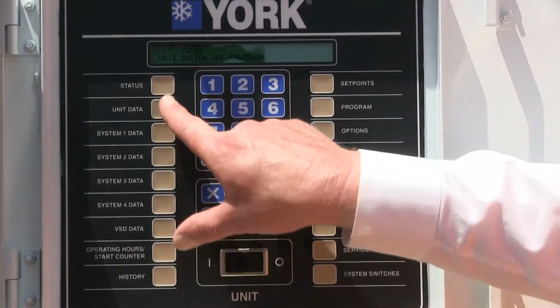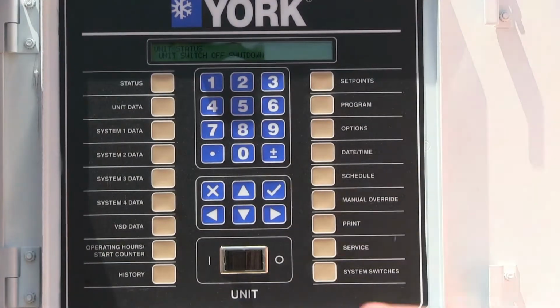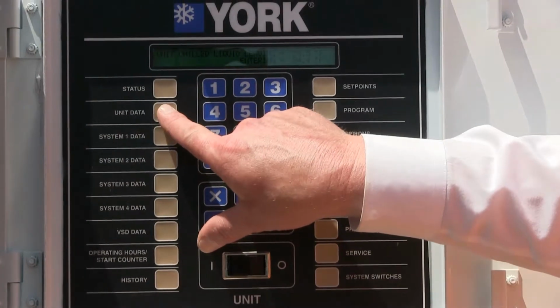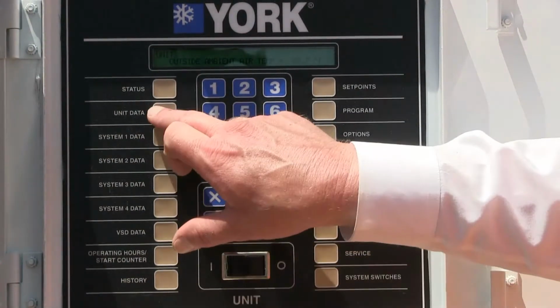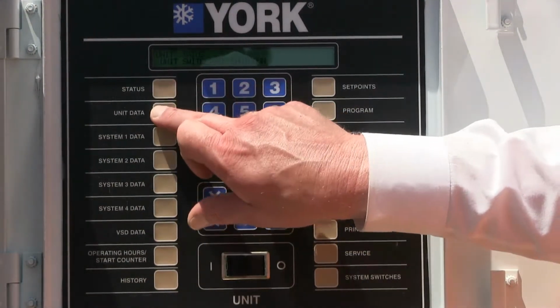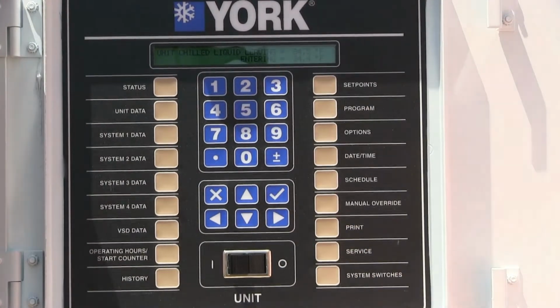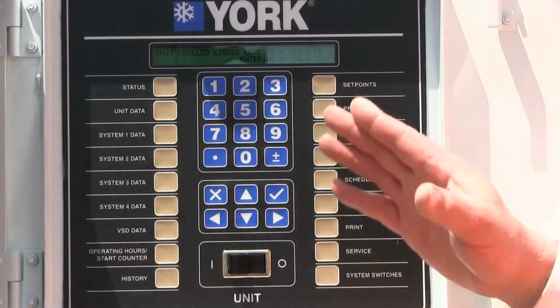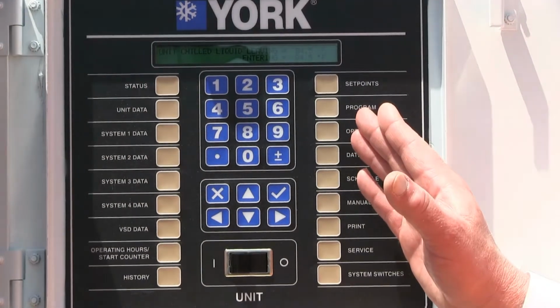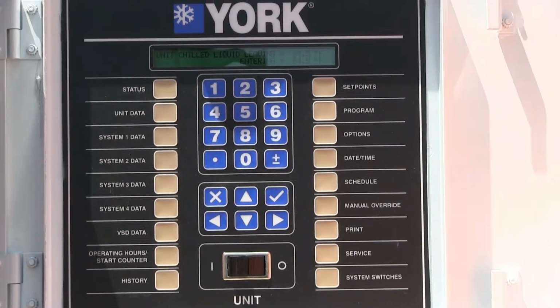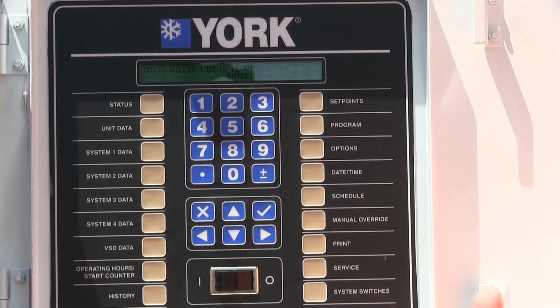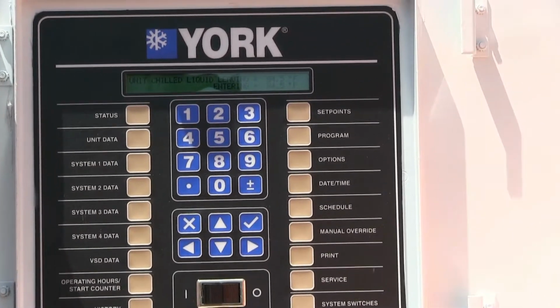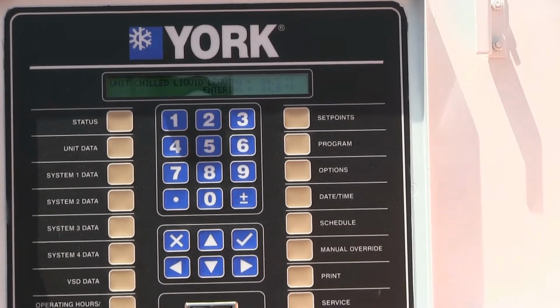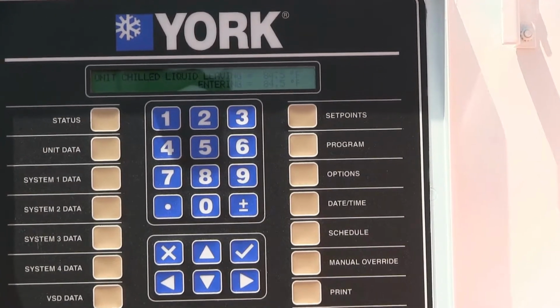So let me run through the buttons. The status is your home screen. The unit data is a very commonly used button. You push it to determine what your water temperatures are. And right now you'll see we've got leaving water temperature of 84.5, entering 84.5. That's a good troubleshooting point to note that both sensors are reading the same value, which indicates both of them are in a healthy state, because we don't have the chiller running right now.